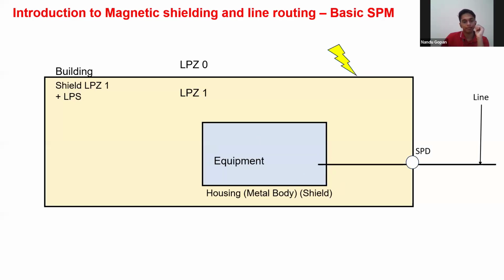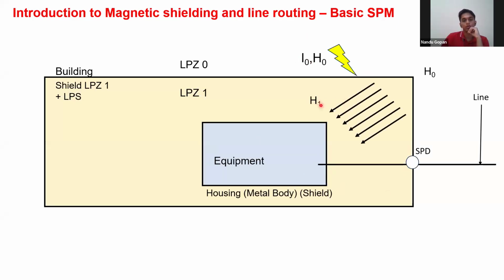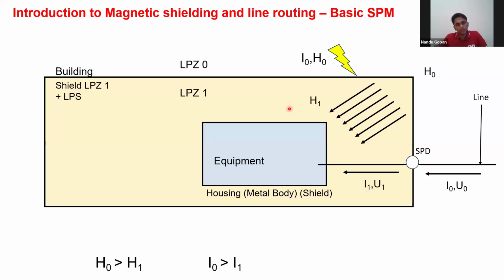In case of lightning, I0 and H0 will be outside, and I1, H1 will be inside. Compared to the previous one, this is a little more cost-effective solution. So if the equipment can withstand this H1 and I1, that is more than enough to have it in zone 1. If it can't withstand it, then you have to go back to the basics as in the previous slide, put another room, and do all those things.